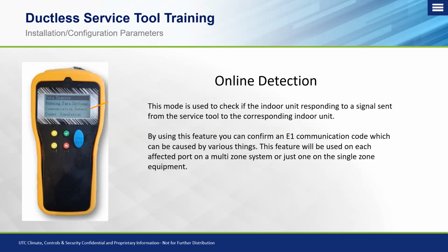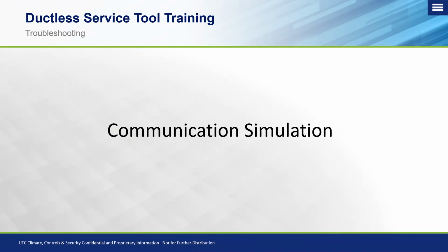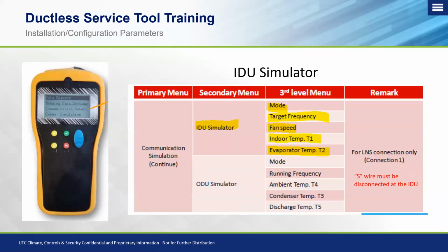Okay, just like we did on the previous feature, except now the tool is mimicking the outdoor unit, sending a control signal to the indoor unit. And you can do that on each indoor unit to make sure that the indoor units are responding. With the communication simulation, you can simulate different scenarios to test the individual indoor unit. Okay, so in this case, we're looking at our indoor unit simulator.